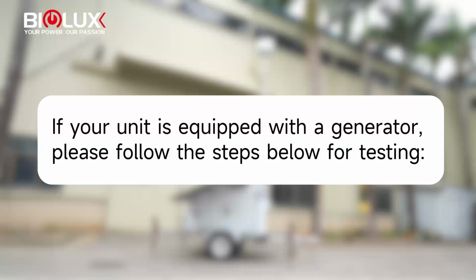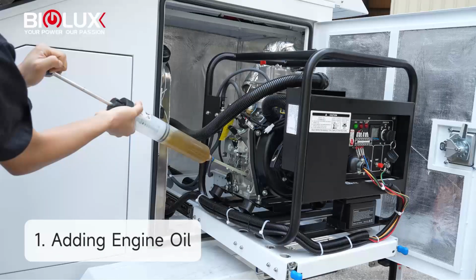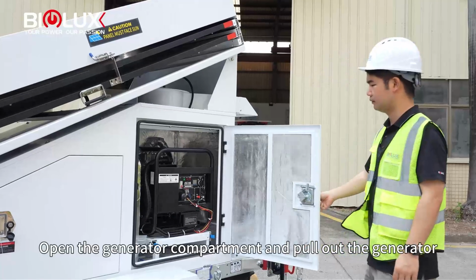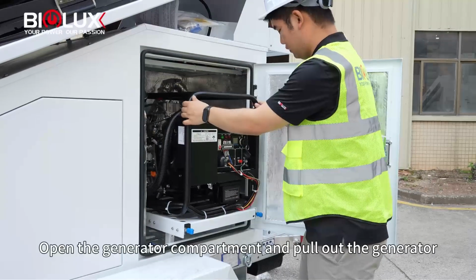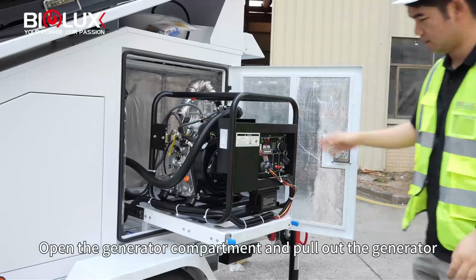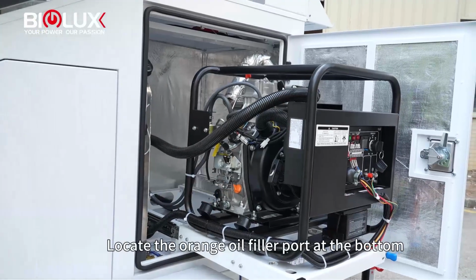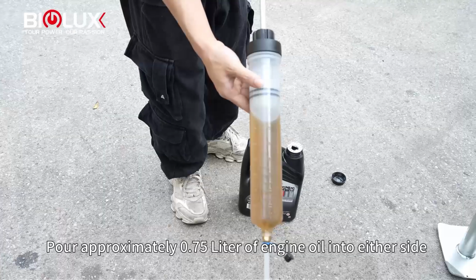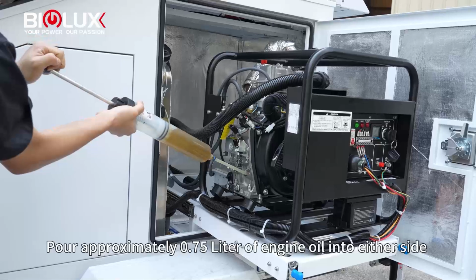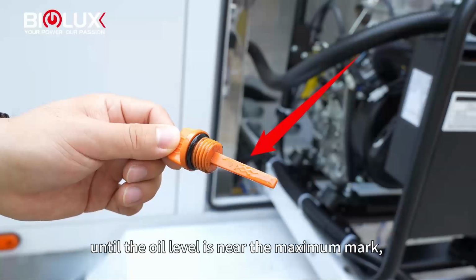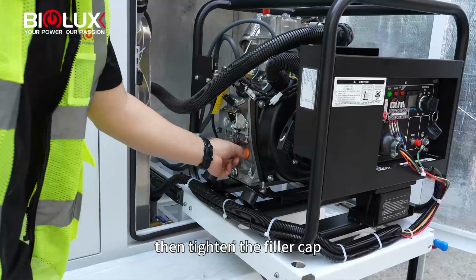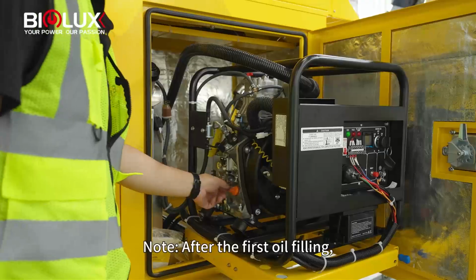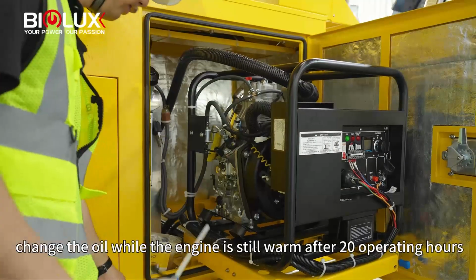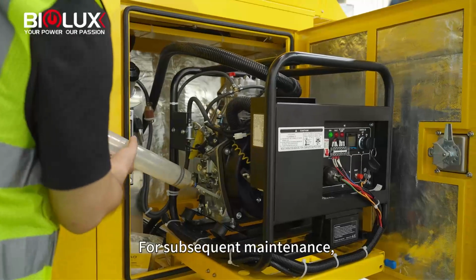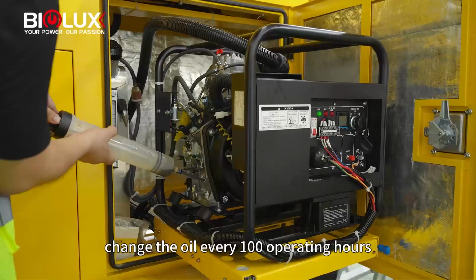If your unit is equipped with a generator, please follow the steps below for testing. 1. Adding engine oil. Open the generator compartment and pull out the generator. Locate the orange oil filler port at the bottom. Pour approximately 0.75 liter of engine oil into either side, until the oil level is near the maximum mark. Then tighten the filler cap. Note, after the first oil filling, change the oil while the engine is still warm after 20 operating hours. For subsequent maintenance, change the oil every 100 operating hours.